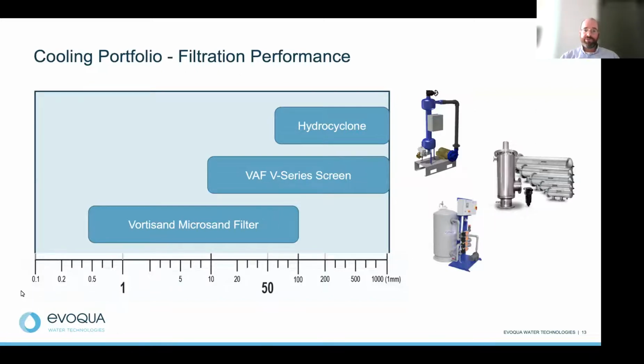First of all is hydrocyclones. Second of all is what we call our VAF automatic self-cleaning screen filter. And lastly, we're going to talk about the Vortisand microsand filter. And we're going to talk about these in order from larger particles to smaller particles. And that's the graph that you see there on the left. It's showing you what size particles these are typically good for getting out of your system. So hydrocyclone separators, they're good at roughly 100 microns and upward. The VAF screen filter, that's great for about 10 microns and upward. And then the Vortisand microsand filter filters all the way down to a half a micron, which is really, really small. So those are the three technologies that Mike will be talking about in more detail here in a minute.